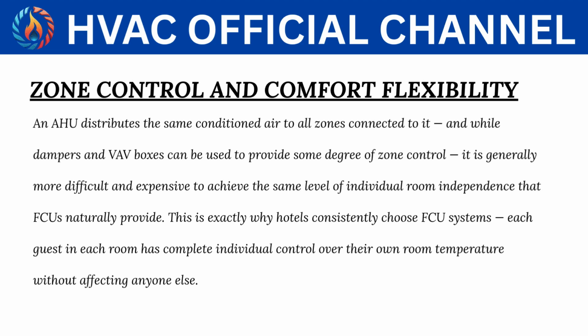An AHU distributes the same conditioned air to all zones connected to it, and while dampers and VAV boxes can be used to provide some degree of zone control, it is generally more difficult and expensive to achieve the same level of individual room independence that FCUs naturally provide. This is exactly why hotels consistently choose FCU systems. Each guest in each room has complete individual control over their own room temperature, without affecting anyone else.